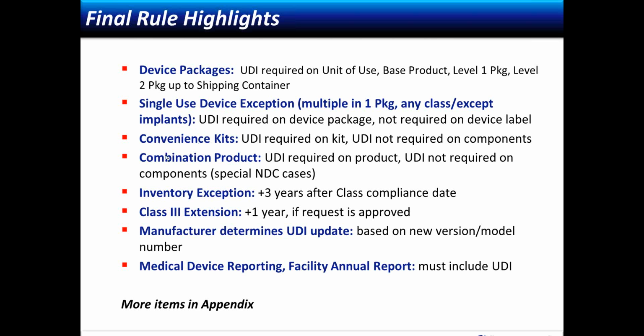One that was very much discussed early on in the proposal phase was convenience kits and combination products. So in a convenience kit, we have multiple products that are assembled together. The bottom line in this particular case is that the UDI would need to be applied at the kit level, but not at the individual component. In a similar scenario for a combination product, a UDI would be required on the product itself, but the actual constituent components would not need to have a UDI. If that is your case on combination products, you might want to read a little bit more. There are some special cases where NDCs are used for the drug portion of that combination product.